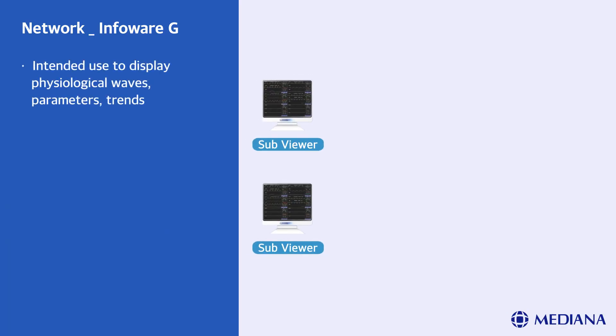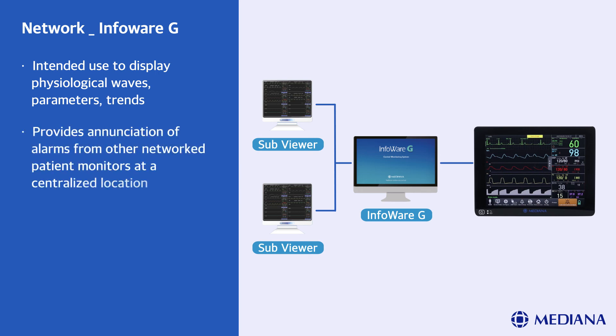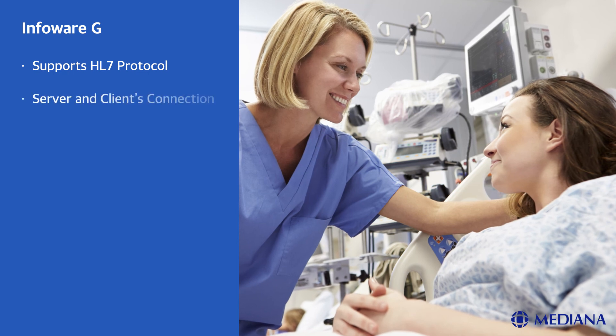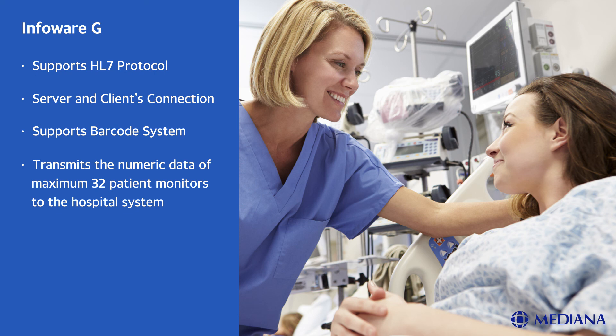The intended use of the central monitoring system is to display physiological waves, parameters, trends and formatted data for strip chart recordings and printings, and provide alarms from other network patient monitors at a centralized location. The central monitoring system provides a retrospective review of alarms, physiologic waves and parameters from its database. It is used in all areas of a hospital and hospital-type facilities. It provides real-time waveform monitoring up to 32 patients being monitored by patient monitors on the system's local area network or wireless access point.